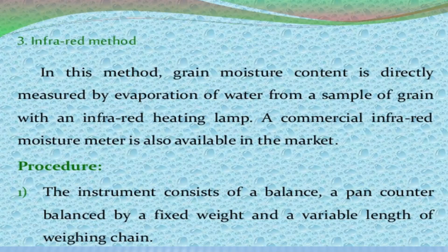The instrument consists of a balance, a pan counterbalanced on a fixed weight and a variable length of weighing chain. An infrared lamp is mounted on an arm above the pan with provision to change its height. A scale calibrated in percentage moisture content is incorporated in the stem of the instrument.